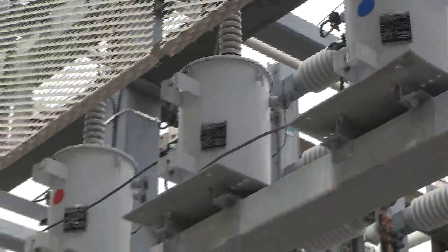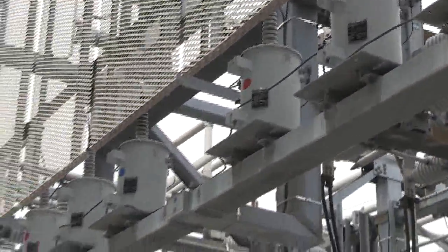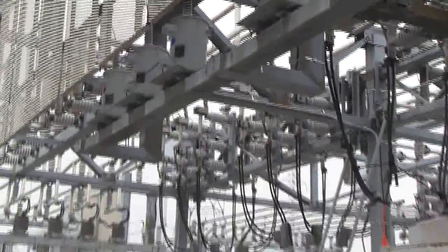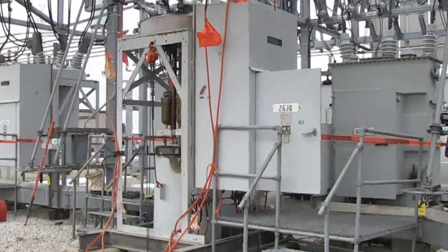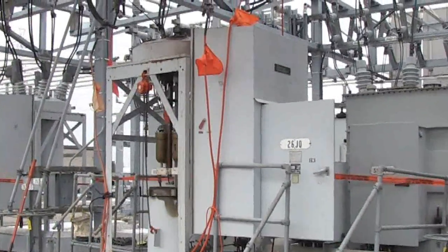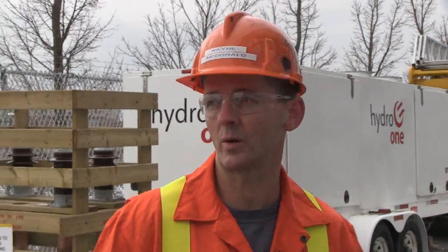If I want to take a component out, in this case an oil breaker, do maintenance on it, I can close a tie switch which bypasses it, so we can take it out and work on it safely but not affect the end user. I believe our high voltage system's in good shape. We run a really good maintenance program.